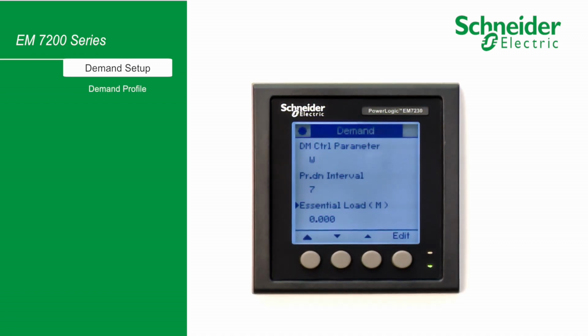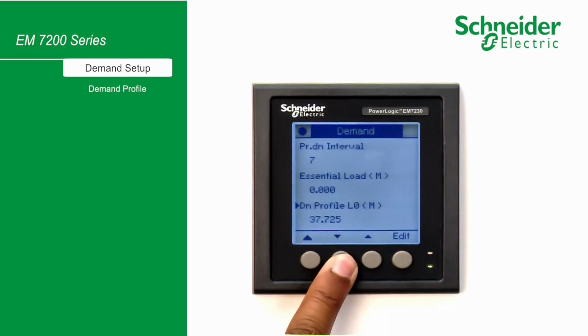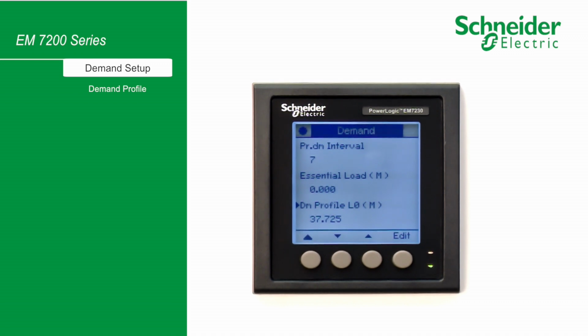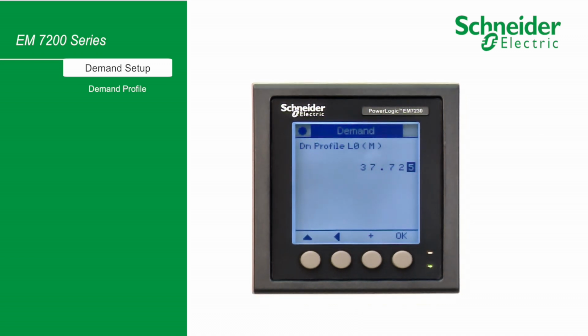Demand controller gives you the option of generating comprehensive 19 levels of demand profiles. That means by the end of the day or week or month, you would know the demand pattern, such as how many times specific demand values reached a particular level. This would enable you to select a reasonable demand value for optimizing your demand charges.